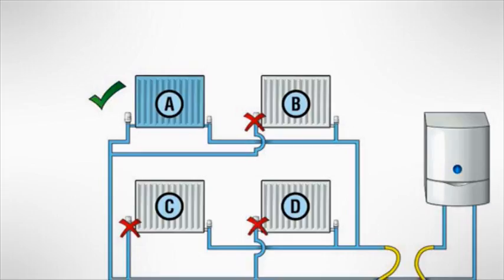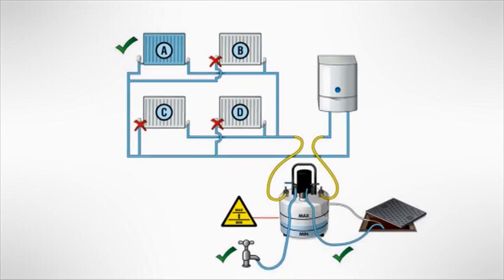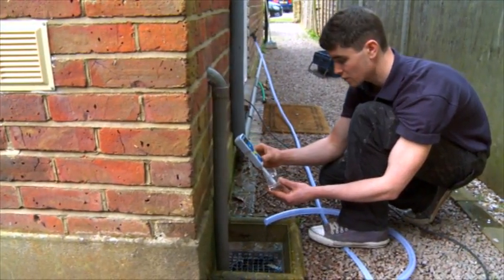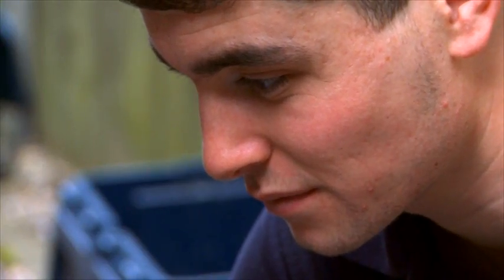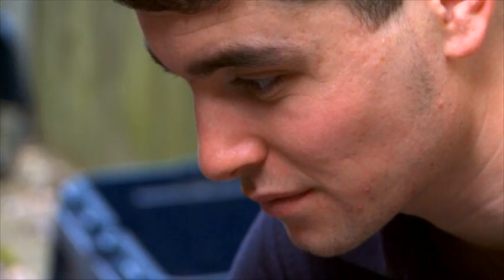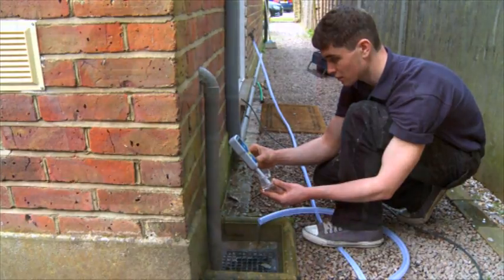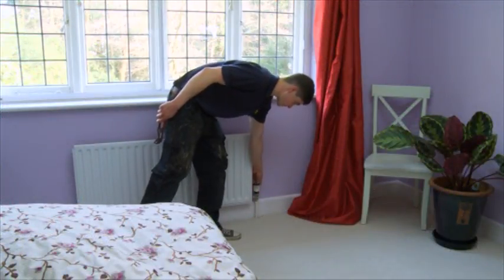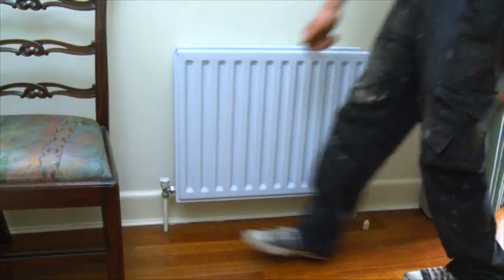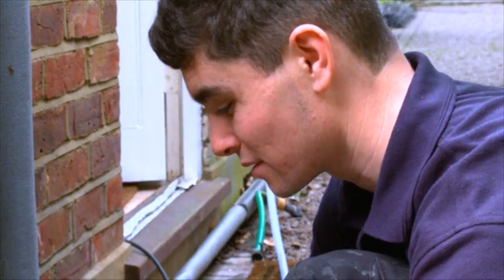For all systems, isolate and clean the downstairs radiators first, as downstairs radiators tend to be more affected by sludge and scale. Monitor the discharge at the drain using the Fernox TDS meter and continue flushing until the water runs clean and the reading is within plus or minus 10% of the mains water. Differences above 10% mean that significant dissolved solids have been left in the system. Only when the discharge is clean, turn off the isolated radiator and repeat the process for all radiators. At each stage, check using the TDS meter that the water is completely clean.